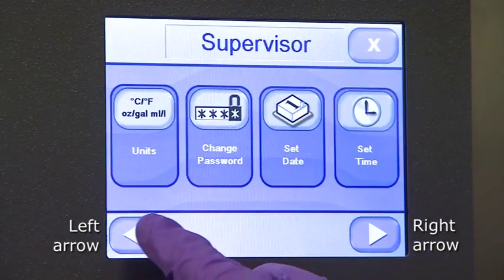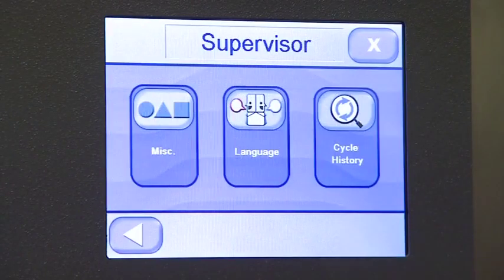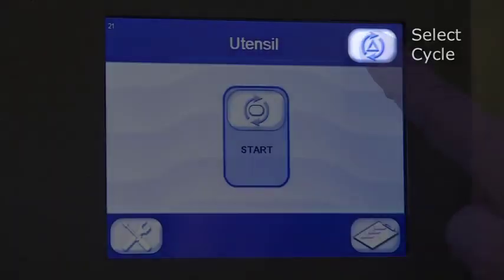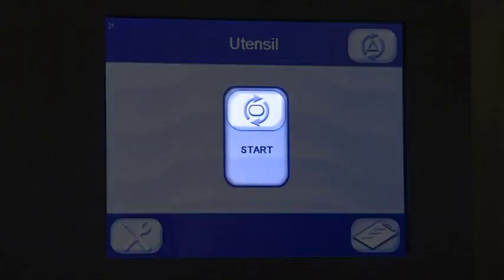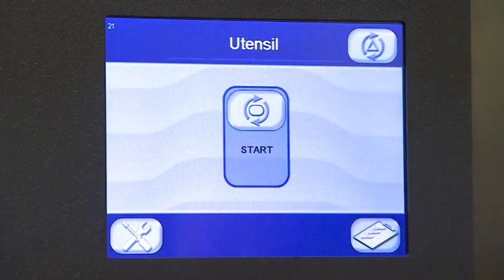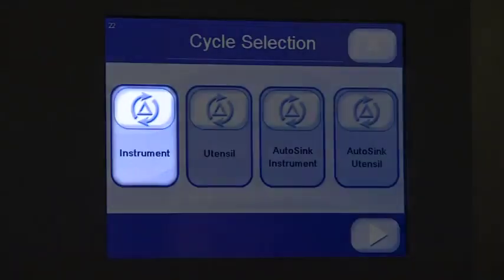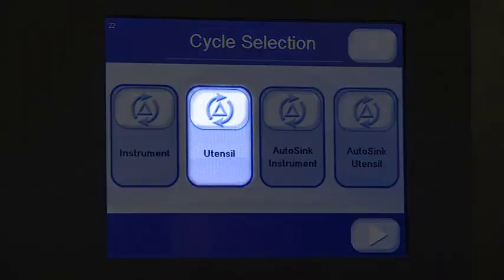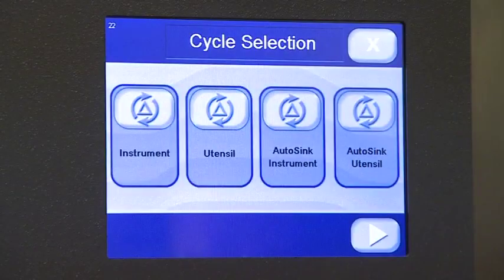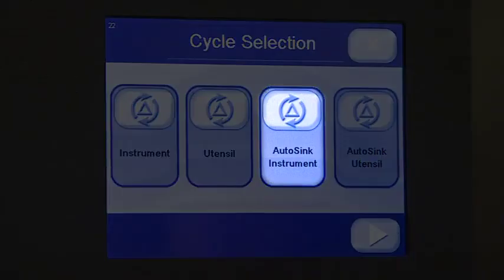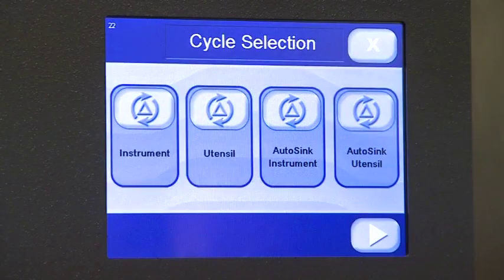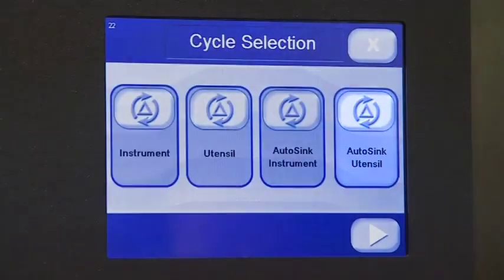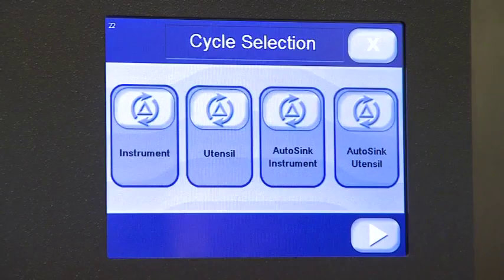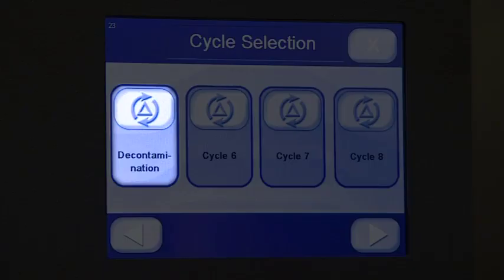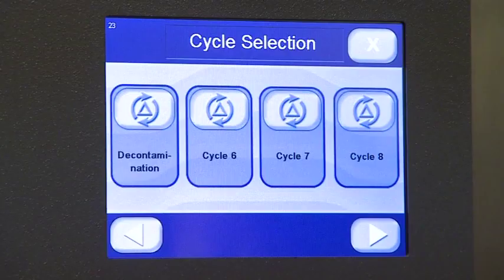Left or right arrow. For forward and back navigation, press left or right arrow. Select cycle. Press this button to select a cycle to start. Start. Press Start to start a cycle. Instrument. This button selects the pre-programmed instrument cycle. Utensil. This button selects the pre-programmed utensil cycle. AutoSink instrument. This button is used to select the pre-programmed immediate wash cycle to process surgical instruments. AutoSink utensil. This button selects the pre-programmed immediate wash cycle to process basins and wash bowls. Decontam cycle. This button processes the pre-programmed locked decontamination cycle.